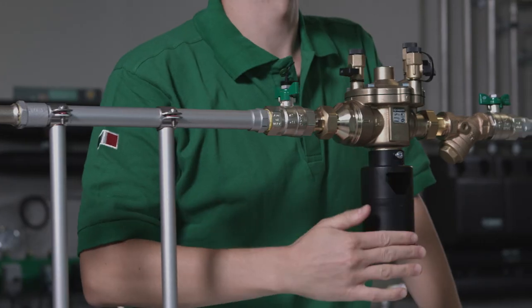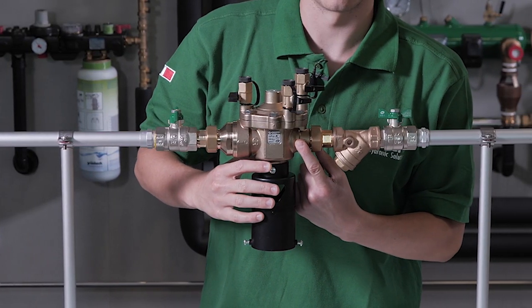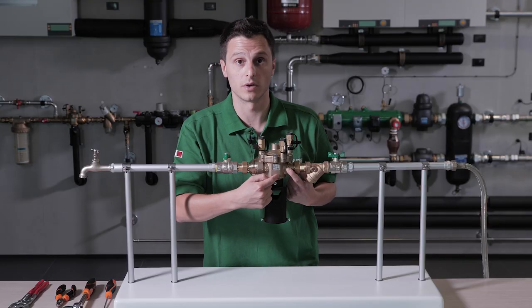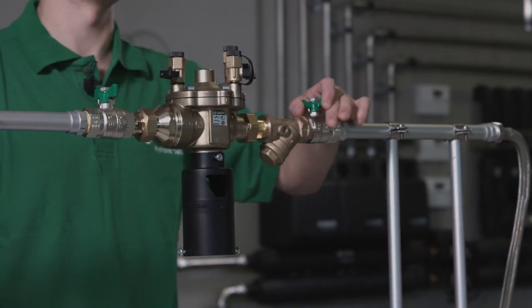and the backflow preventer keeps on leaking, it means that we have a failure in the upstream check valve or in the discharge valve, which is the central component of the backflow preventer.